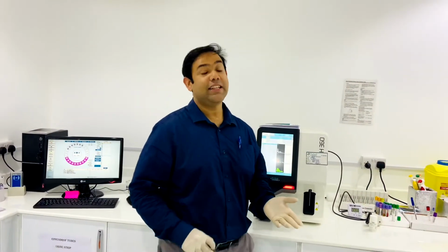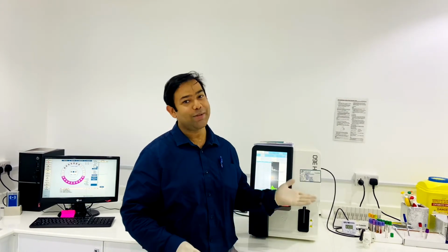So guys, in this analyzer you can run whole blood mode as well as pre-dilution mode and capillary mode, because there are many analyzers in which you cannot run the sample in pre-dilution mode. Pre-dilution mode is very good especially for peds, where you cannot withdraw a large quantity of blood. For peds, from just one drop of blood you can run this CBC test.